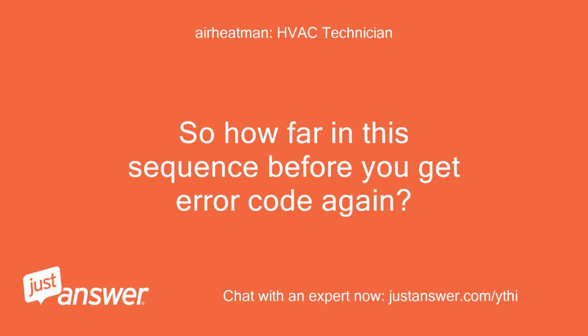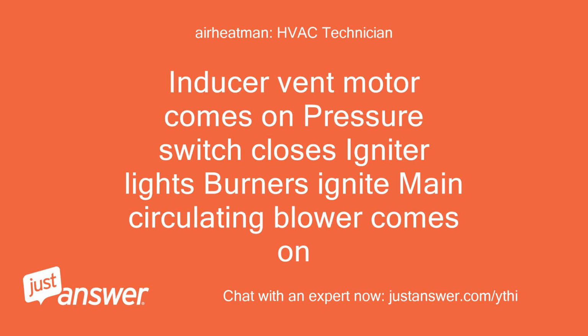So how far in this sequence before you get error code again? Inducer vent motor comes on, pressure switch closes, igniter lights, burners ignite, main circulating blower comes on.